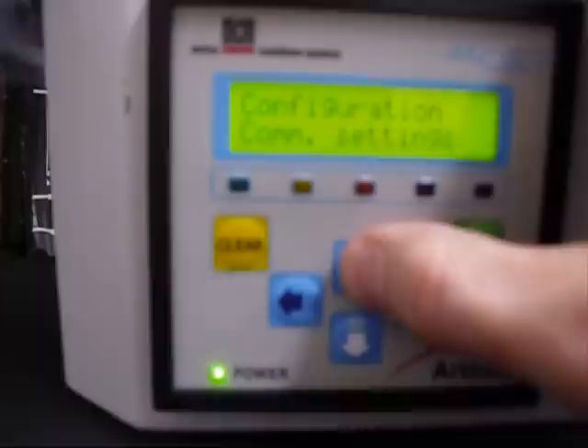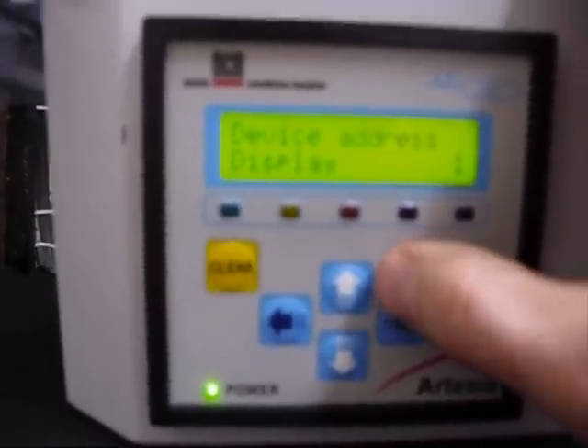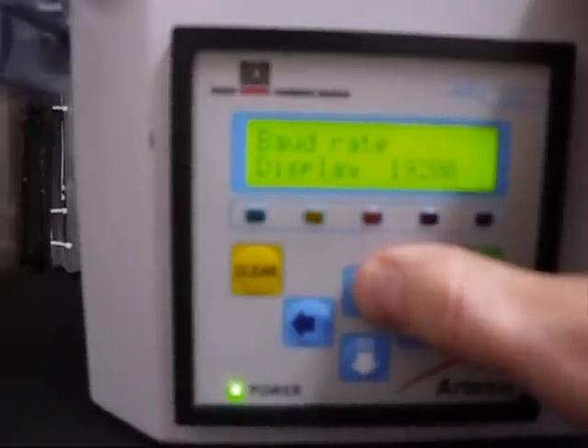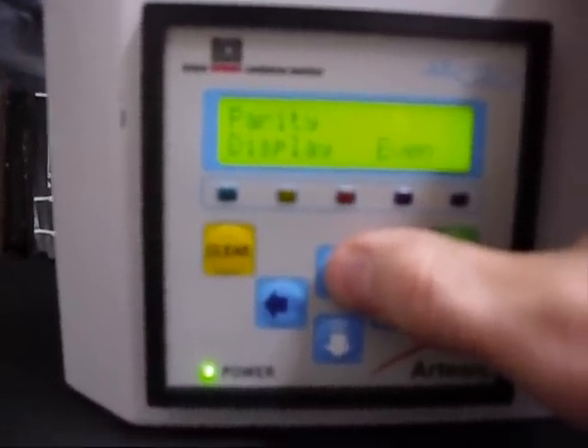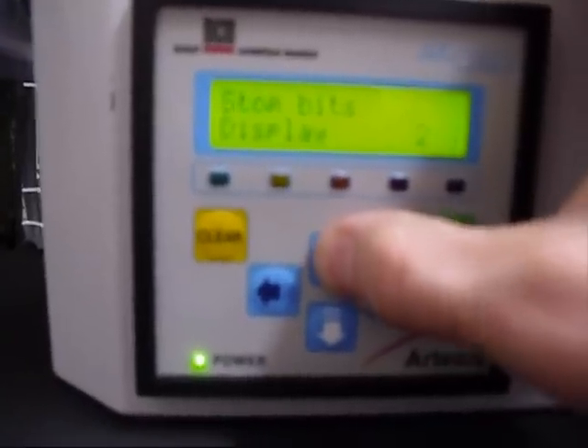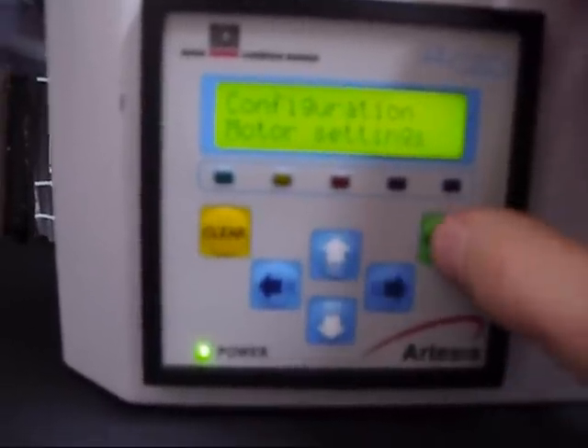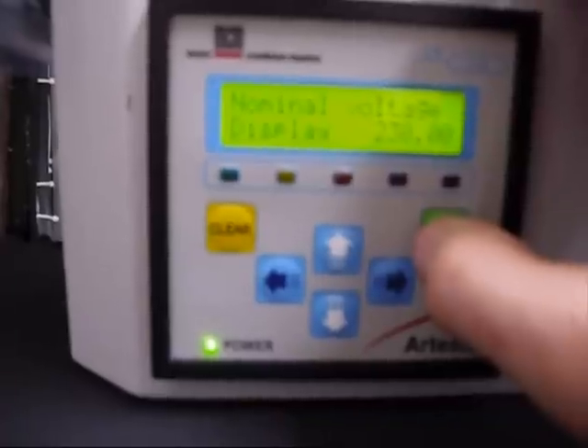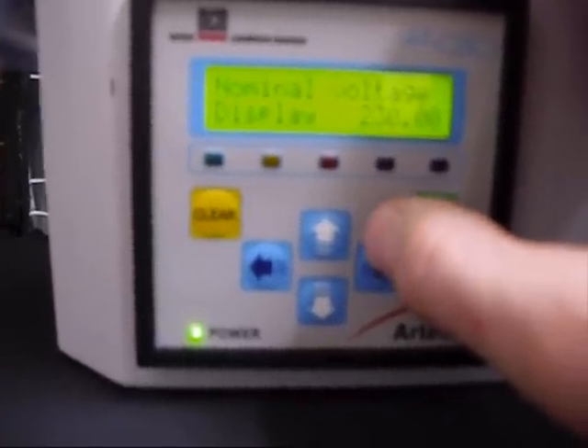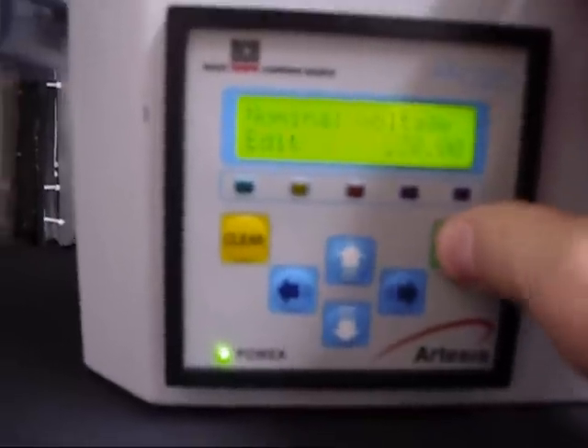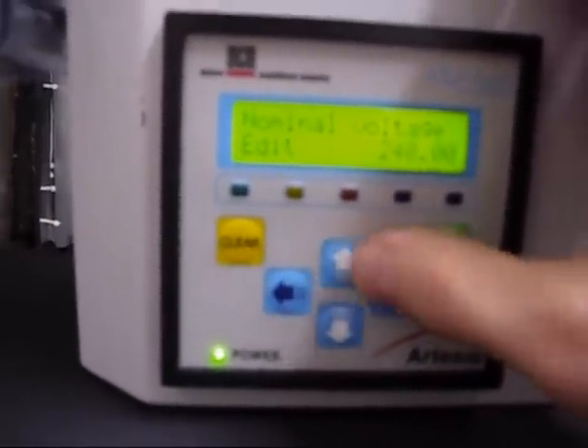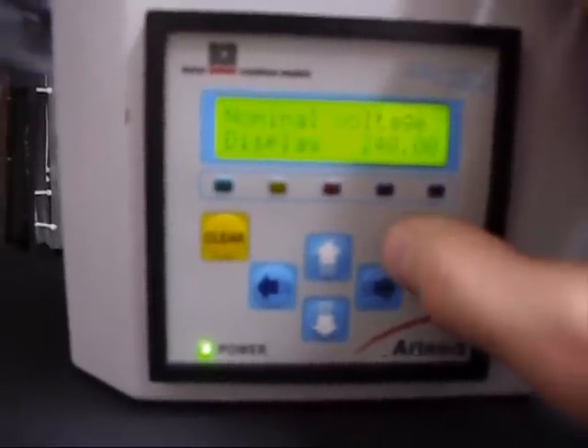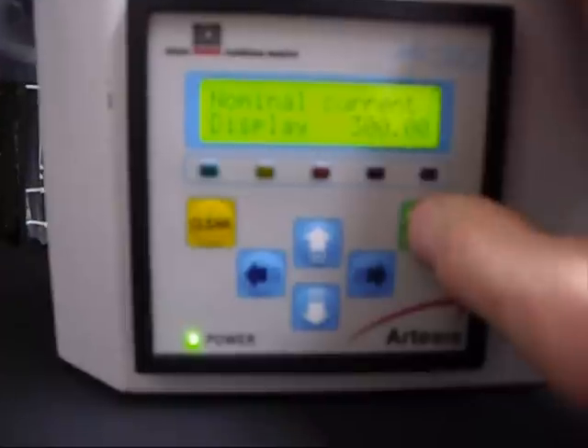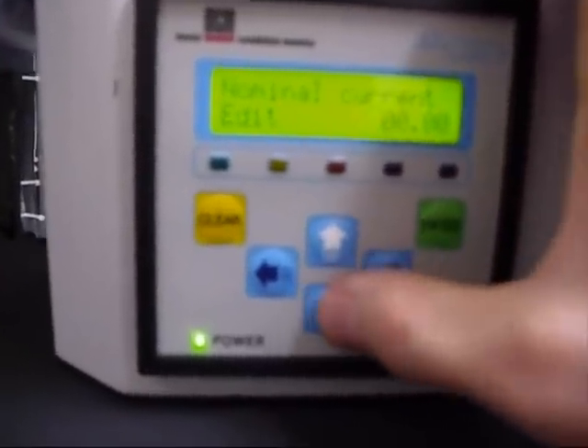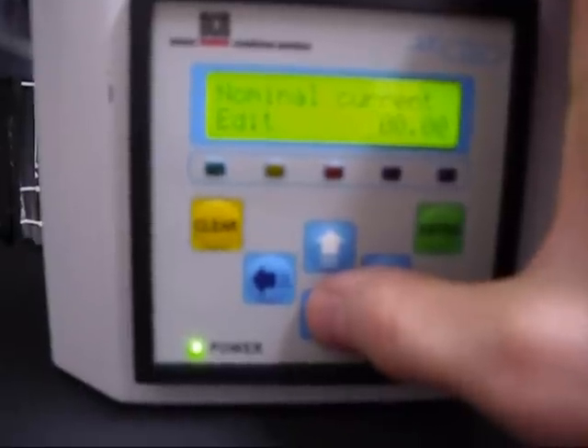Okay, so the first thing we're going to check is the COM settings. Device address number 1, 19,200 baud, even parity, data bits 8, stop bits 2. This is fine, so we can leave it. Motor settings. So we're on 450 volts. Per phase voltage is going to be around about 240. So we'll change this to 240. Enter, enter confirms it. Nominal current. Well, on the faceplate it says 66.5, so that's what I'm going to enter.